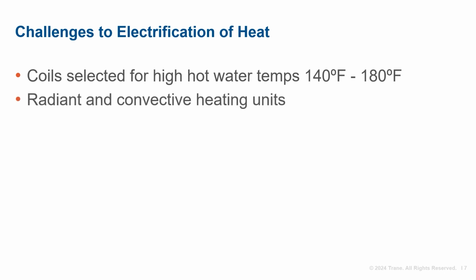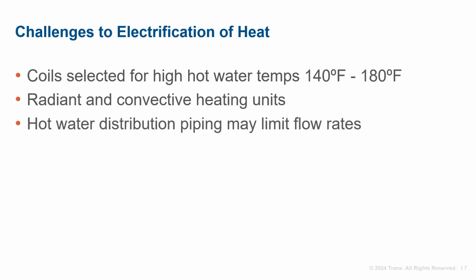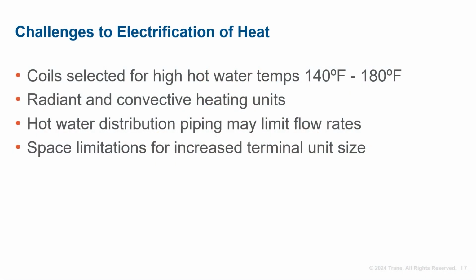Radiant and convective units, whose capacity is closely tied to hot water supply temperature, may be difficult to address. Hot water distribution piping, sized for as high as 30-degree delta Ts, may limit hot water flow rates. As hot water supply temperatures drop, it may be necessary to increase the size of terminal units. The ceiling, plenum, or mechanical room dimensions may limit how large these components can get.